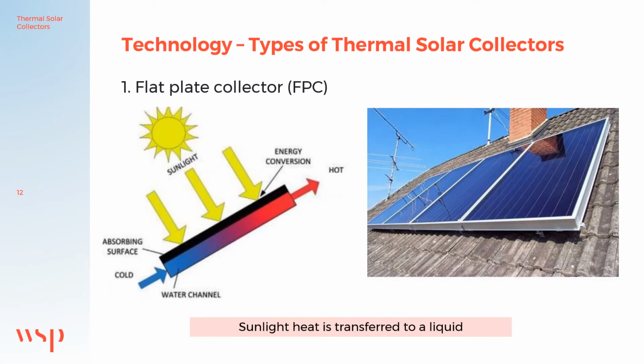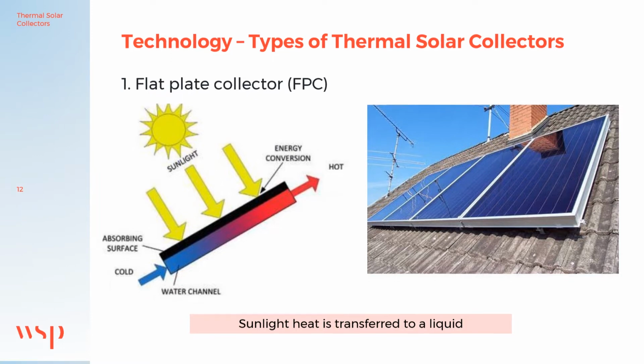The most common and cheapest type of thermal solar collector is the flat plate collector, or FPC. Heat from sunlight is transferred to a liquid that flows through pipes inside the collector. The liquid is typically glycol, which is a mixture of water and antifreeze agent, and that is used to prevent freezing due to frost or snow. The cold liquid enters the bottom and the hot liquid exits at the top.